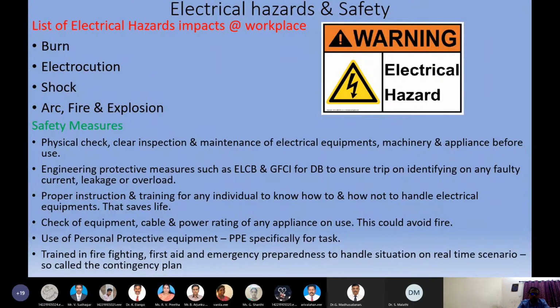As engineering protections, ELCB and GFCI, the earth leakage circuit breakers and ground fault circuit interrupters, you would have studied these in your education systems as well. ELCB is mostly used for 230 volt power supplies, and GFCI is mostly used for 110. In countries where we work, like UAE, Oman, and Bahrain, they use ELCB at 220 volts, while in Saudi Arabia and Qatar, they use GFCI, ground fault circuit interrupters.